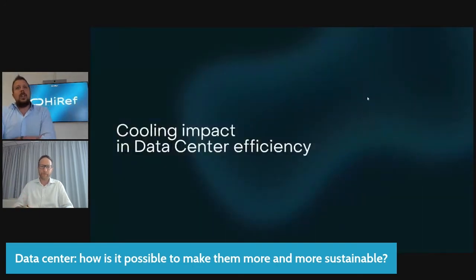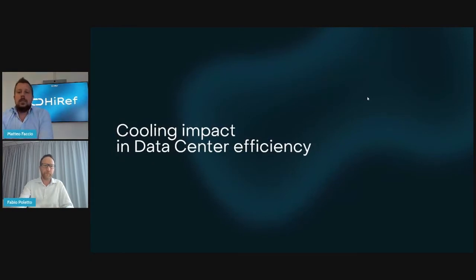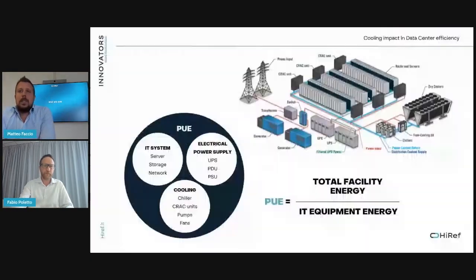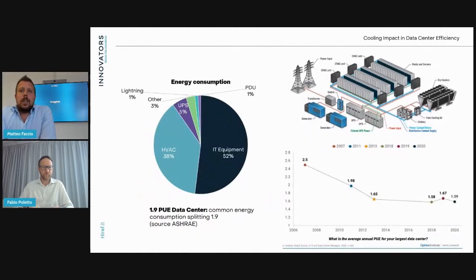Yes, I think we need to look at the cooling impact on data center efficiency. But first of all, having an overall view of a data center, we can see a system that is using a lot of energy. Everything inside is absorbing energy. And of course, everybody knows what a PUE is. So focusing our attention on how the PUE is determined, we can look at this graph, which represents a PUE of 1.9.